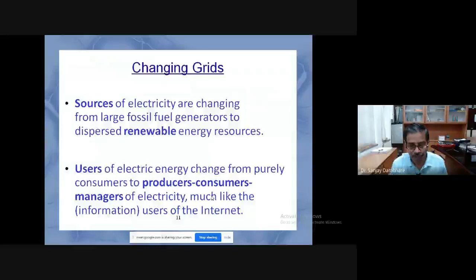When you are talking of high voltages, you are availing this large SIL, and that facilitates transmission of large power. But on the other side, your X by R ratio is increased. As the voltage increases, the X by R ratio increases, and this will create some problem which possibly needs some compensation and so on.